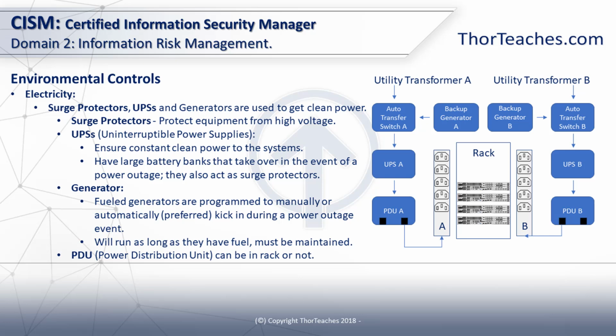Remember, that's the uninterruptible power supply. That's the large battery bank. If the power's good and everything's clean, the UPS really just sits there with the fully charged batteries and does nothing. It lets the power pass through. Maybe not pass through, but it won't start depleting its own battery if it's getting clean power. As soon as it doesn't get enough power, it'll start using the batteries.